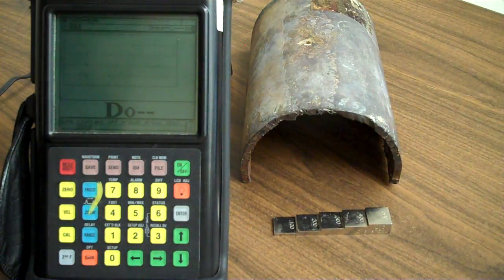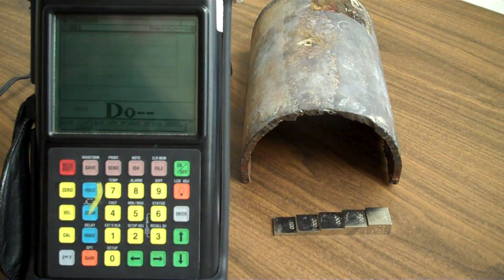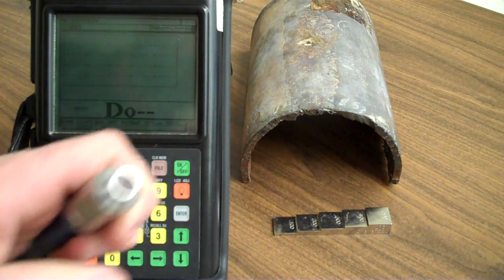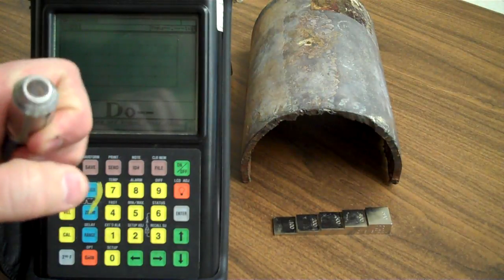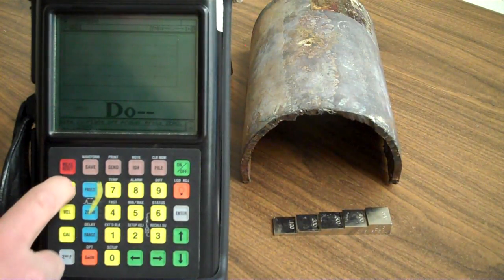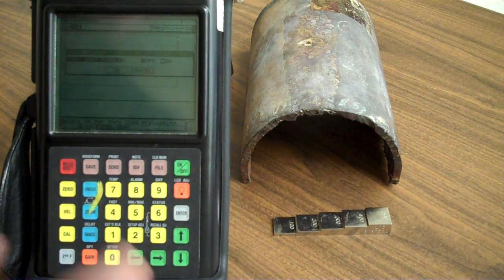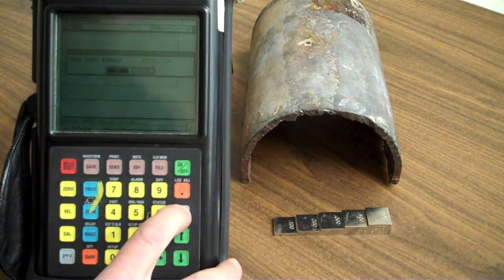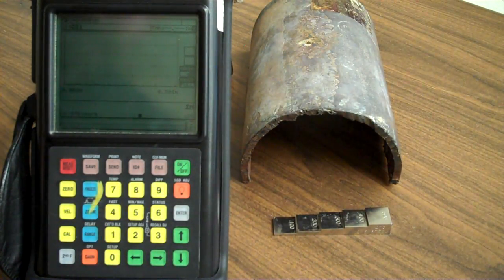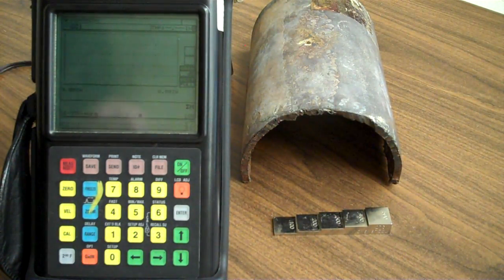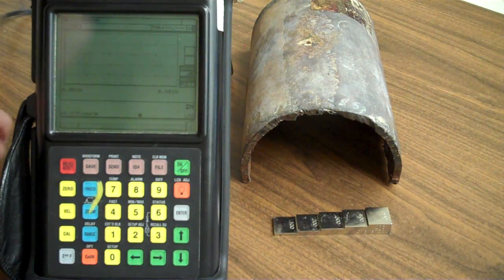So, first things first, got to calibrate our machine. I'm just reading the prompts here. Wipe the couplant off the probe, press 0. Okay, got my probe here. This is a dual element probe, so I'm going to press 0. I don't need through coat enable right now because I don't have any coating on this. So the biggest thing here is we have to make sure we are calibrated. So get me a little couplant.